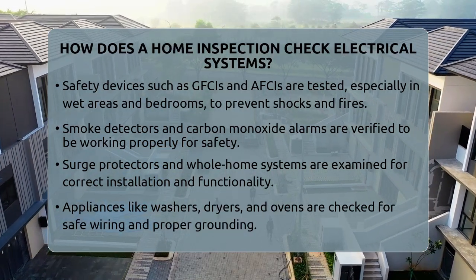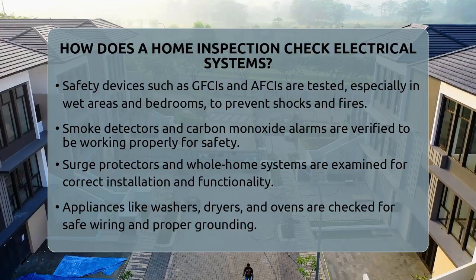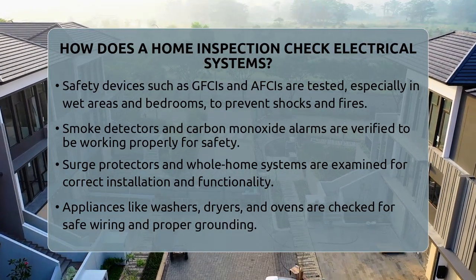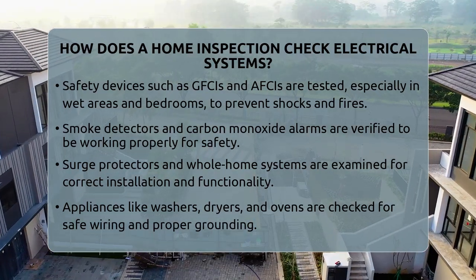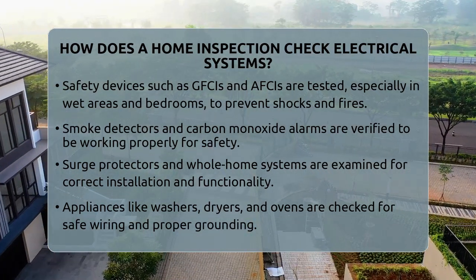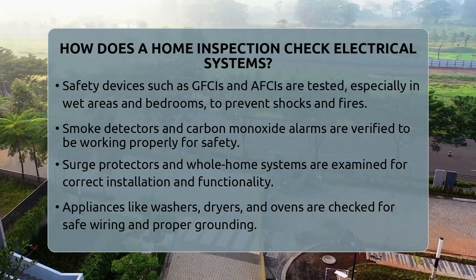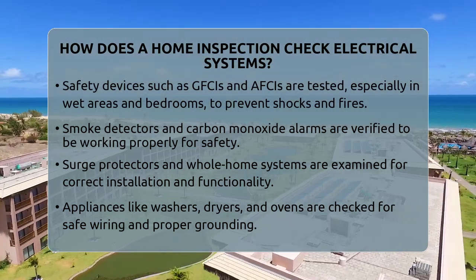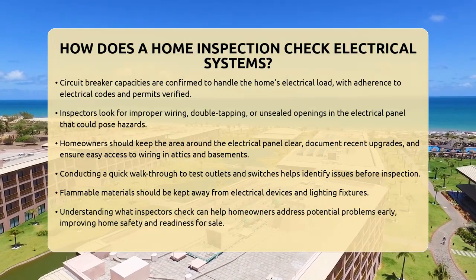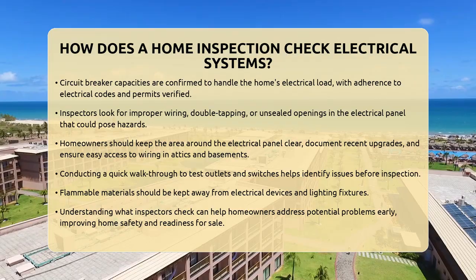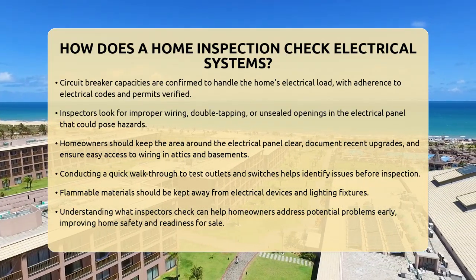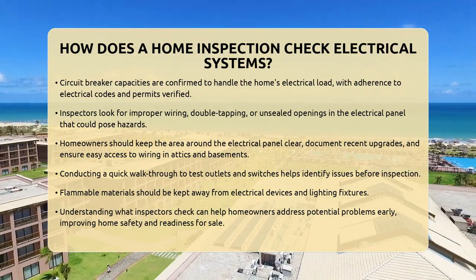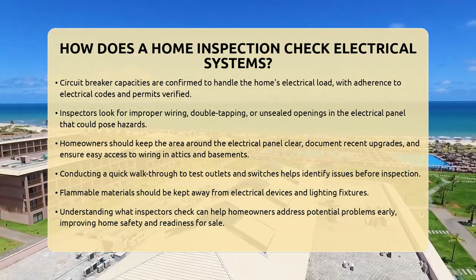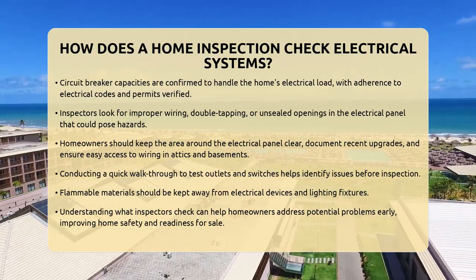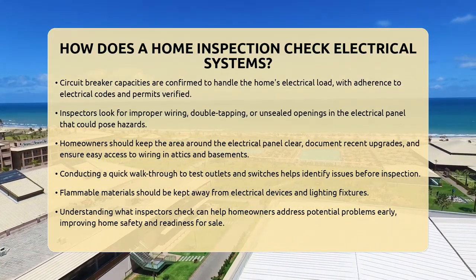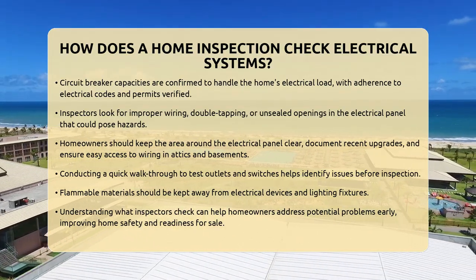Surge protectors and whole home surge suppression systems are examined to ensure they are installed correctly and functioning. The inspector also looks at appliances like washers, dryers, and ovens, making sure their wiring and connections are safe and properly grounded. Circuit breaker capacities are checked to confirm they can handle the total electrical load of the home. All electrical work must meet the National Electrical Code and local regulations. Inspectors verify that any electrical modifications or additions have the proper permits and inspections. They look for improper wiring, double tapping, or unsealed openings in the electrical panel, which can be hazards.